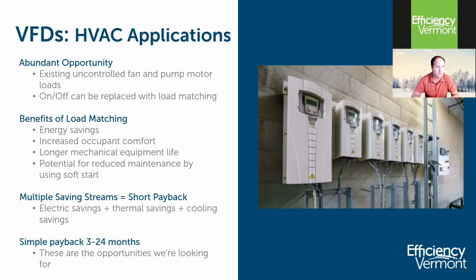The fan energy is about 5% of the overall energy consumed. 95% of it is the rejected heat out of the building, which your boiler or furnace or other heating system has to make up for. So sometimes it's about electric savings, and in the case of exhaust fans, it's really more about the BTU savings. And if it's a cooled space, you'll get some derivative kilowatt hour savings from reduced cooling rejection as well. As I said earlier, these paybacks are rapid. We have customers often saying, give me something in the 1 to 3 year range. That's kind of the sweet spot for energy efficiency projects. Drives fit very nicely in the 2 years or less. And with our rebates, we can often get them down to a year, maybe sometimes even better.